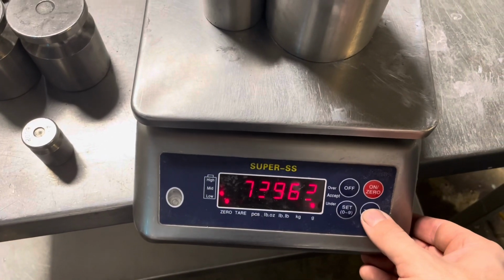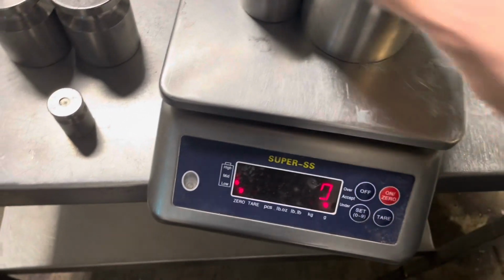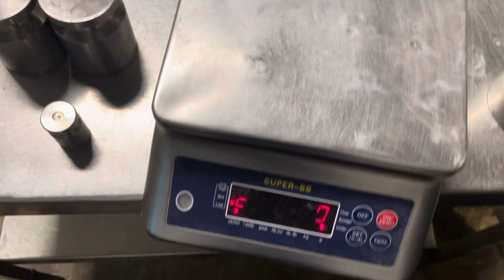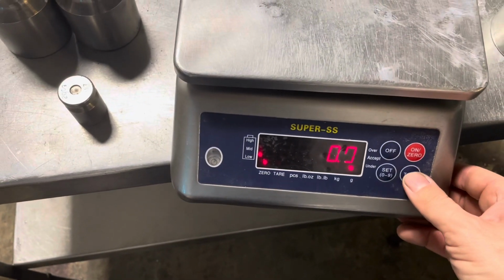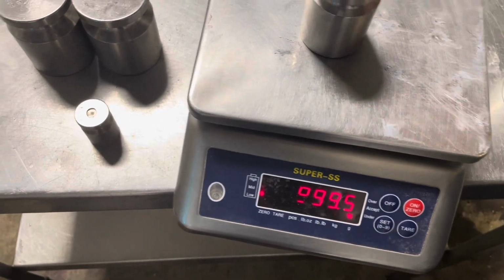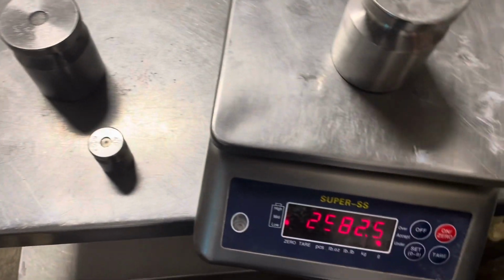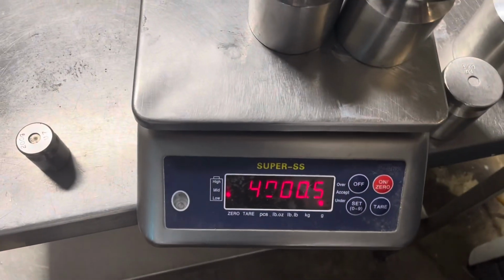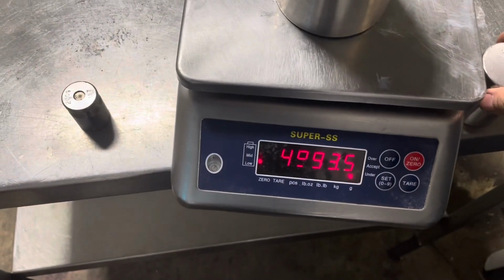And that's how you can get more life out of your scale without having to replace it, because everything is so daggone expensive these days. And once you're all done, you test the scale by putting the weights back onto it. So if you have any questions, comments, concerns, please leave them down below. But again, this is a generic scale. Anybody can calibrate it. You just have to unlock the scale so that you have access to the calibration menu.